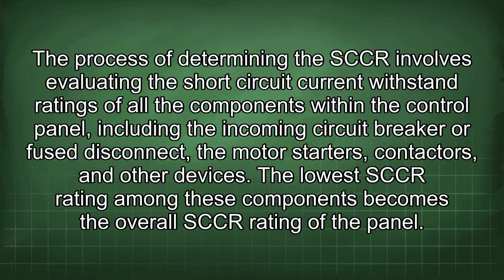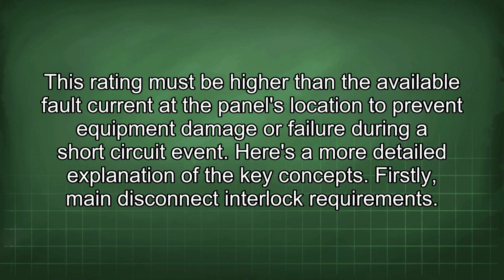The process of determining the SCCR involves evaluating the short-circuit current withstand ratings of all the components within the control panel, including the incoming circuit breaker or fuse disconnect, the motor starters, contactors, and other devices. The lowest SCCR rating among these components becomes the overall SCCR rating of the panel. This rating must be higher than the available fault current at the panel's location to prevent equipment damage or failure during a short-circuit event. Here's a more detailed explanation of the key concepts.